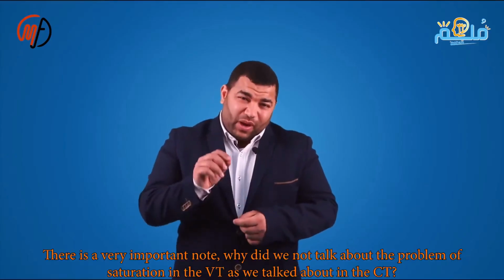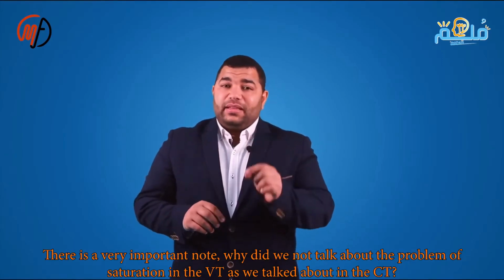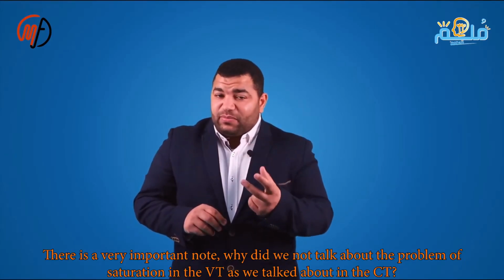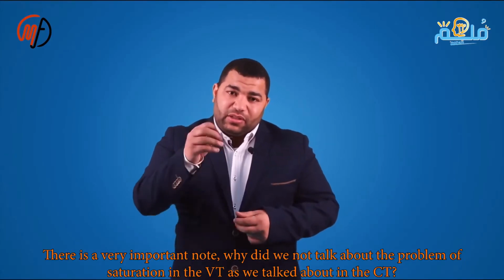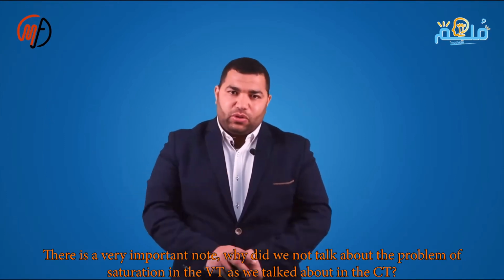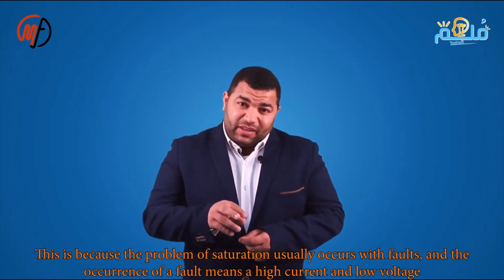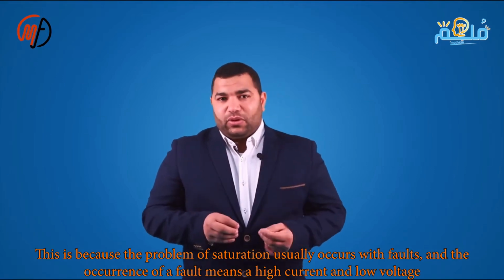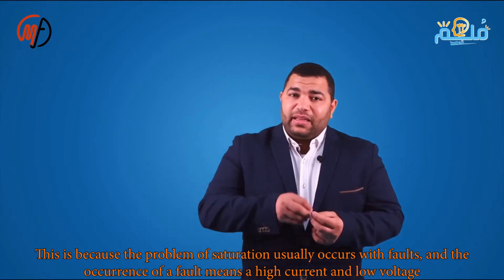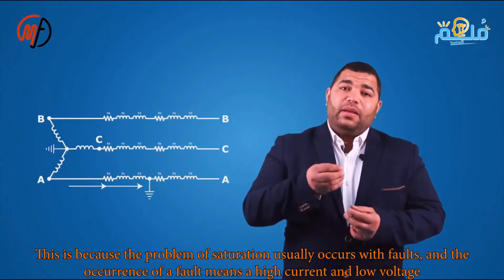But there's a question. Why didn't we address the saturation issue in VTs, voltage transformers? That's because saturation problems occur with faults. If there's a fault, this fault creates high current, lowering the voltage. So when there's a drop in voltage, it may not affect the VT and it might not saturate. Therefore, the saturation issue is not widespread in VTs, though saturation can occur in VTs if there's an overvoltage.